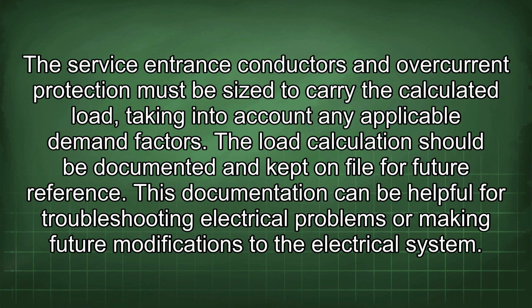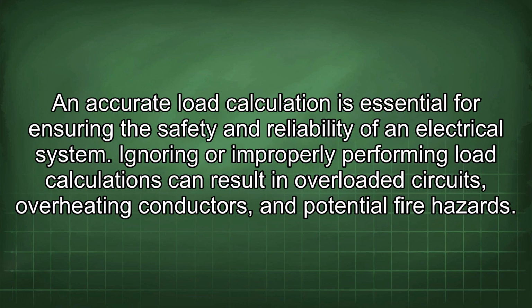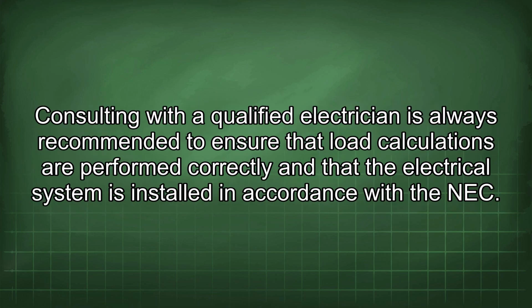This documentation can be helpful for troubleshooting electrical problems or making future modifications to the electrical system. An accurate load calculation is essential for ensuring the safety and reliability of an electrical system. Ignoring or improperly performing load calculations can result in overloaded circuits, overheating conductors, and potential fire hazards. Consulting with a qualified electrician is always recommended to ensure that load calculations are performed correctly and that the electrical system is installed in accordance with the NEC.